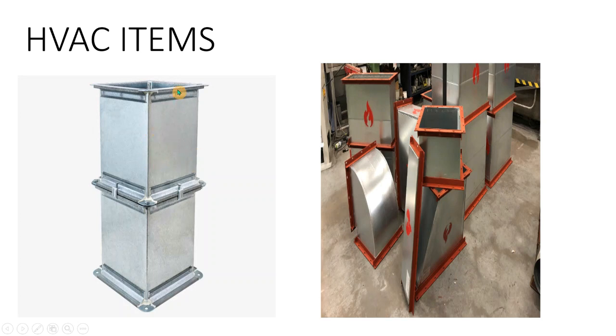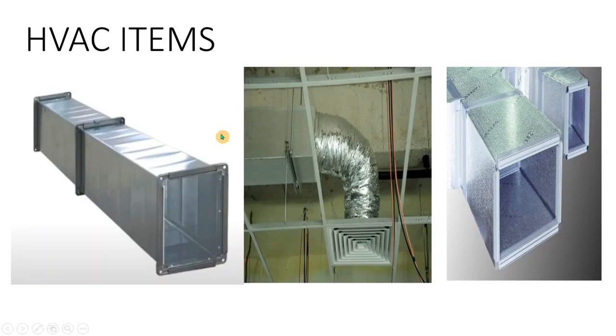The fire rated duct generally will have 1.2 mm thickness. But when it comes to GI, the thickness can start from 0.6 mm and go all the way up to 1.2 mm. For the PI duct, plenty of options are available. PI stands for pre-insulated duct. When you buy the PI sheet from the supplier or manufacturer, you yourself, with the help of your ductman, can fabricate this duct at your construction site. It will not take much time. Also, the price of this duct is comparatively low when compared to the GI duct.